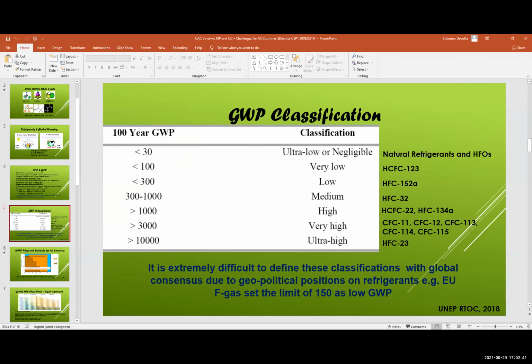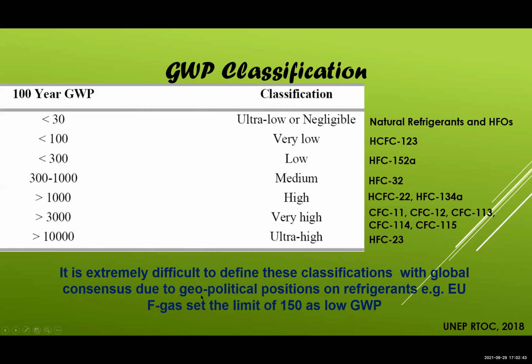I just wanted to go back to this. The debate started when the EU put the F-gas limit at 150. They wanted to limit refrigerants higher than 150, not acceptable for mobile air conditioners. But now they are limiting refrigerants to 150 in many applications, and some of the countries have started imposing carbon tax depending on the GWP. So high GWP means you pay more, not only for the price, but also tax.